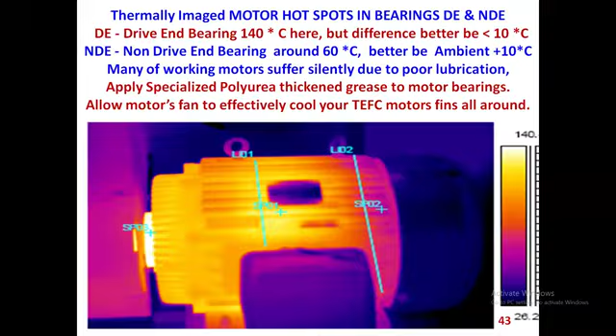the motor's health. See, a motor is talked about in terms of the GD squared value for the given load that is coupled to the motor, whereas the motor's thermal health depends upon the temperature rise in the given motor, and if the motor is warm, it is good. If the motor is hot, it is losing its energy, it is running inefficiently. If the motor is cold, it's just idling, it is losing more power than the warm motor as such.